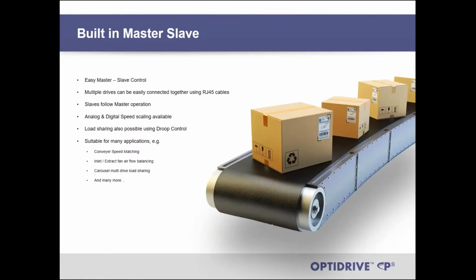Also, you can use it as a master in a network application, in a fieldbus network. This is not available in the E3. If you want to use your drive as a master in a communication system, you will need to use a P2 drive. So you can use, for example, a P2 as a master and E3 as a slave, or you can use only P2, for example, as a slave also.